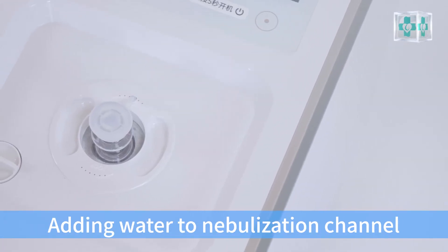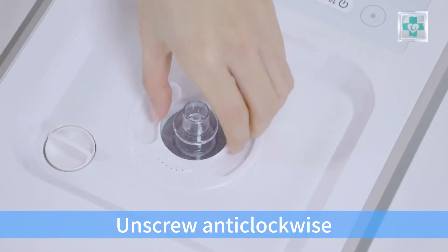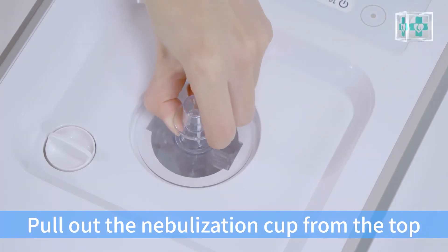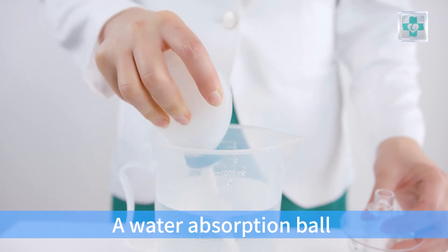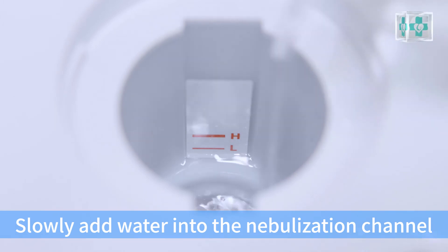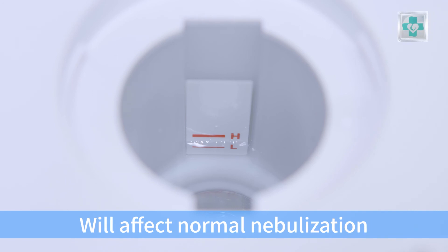Adding water to the nebulization channel and nebulization cap. Remove the rubber plug, screw counterclockwise, and then remove the top cap. Pull out the nebulization cup from the top. Absorb the purified water with a water absorption ball and slowly add water into the nebulization channel. Keep the water level between the H and L marks — a water level that is too high or too low will affect normal nebulization.